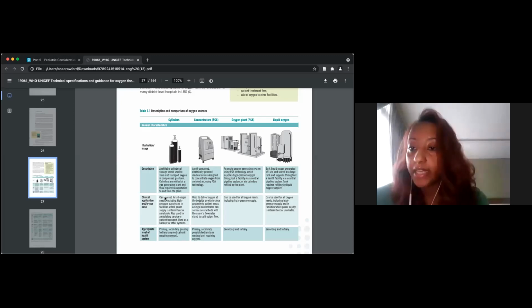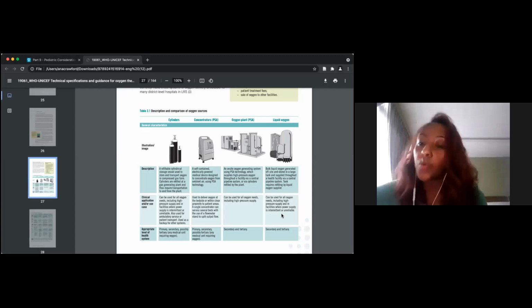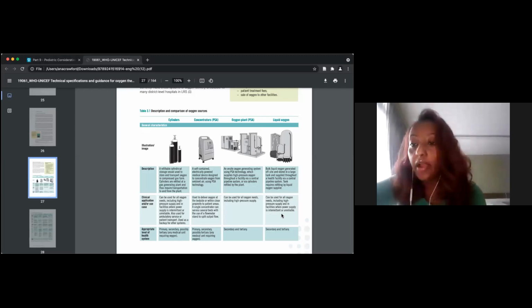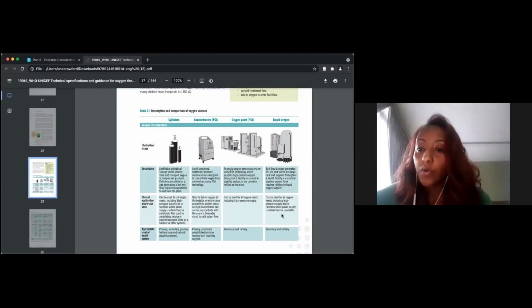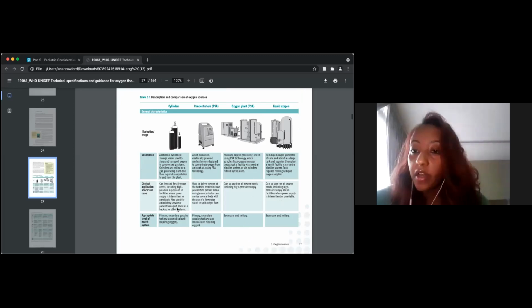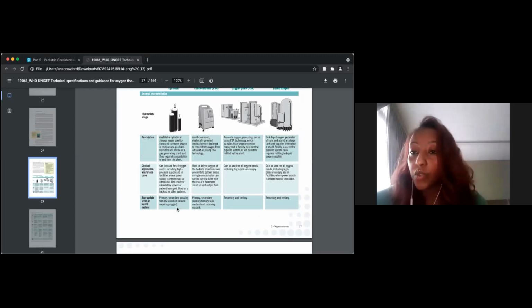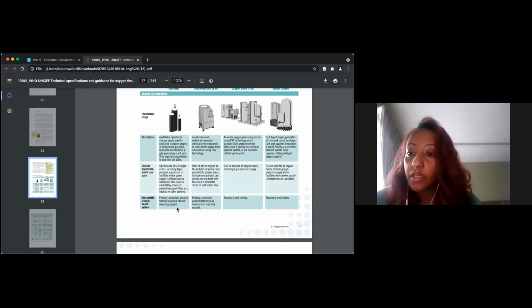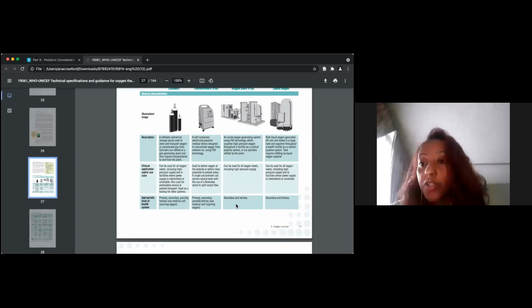When it comes to oxygen plants, they can be used for all oxygen needs, including high pressure supplies. And liquid oxygen can be used for all oxygen needs, including a high pressure supply in facilities where power supply is intermittent or unreliable, as it does not require electric sources. So cylinders can be applied in almost all health systems. Concentrators, primary and secondary, possibly tertiary as well. Oxygen plants can be used in secondary or tertiary level, as they are relatively more advanced. And liquid oxygen definitely in secondary and tertiary, as it's very advanced and requires higher technology.